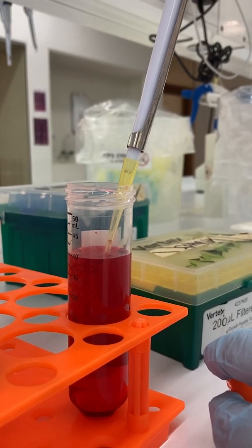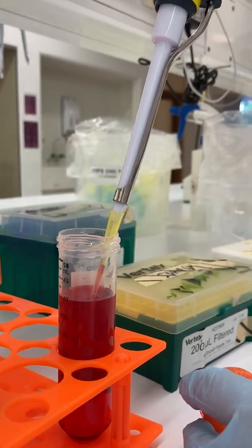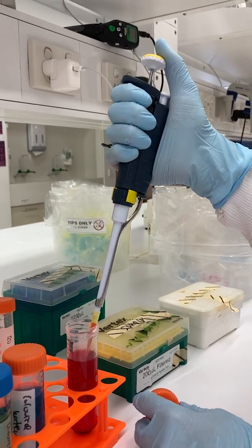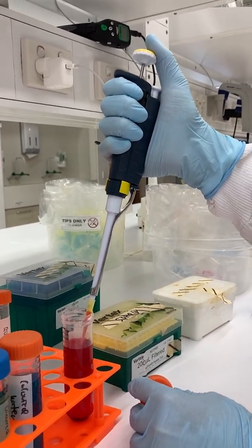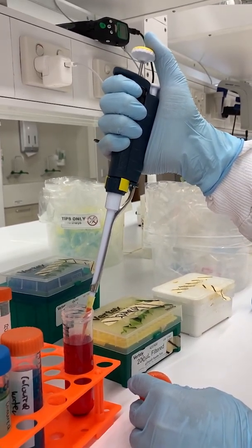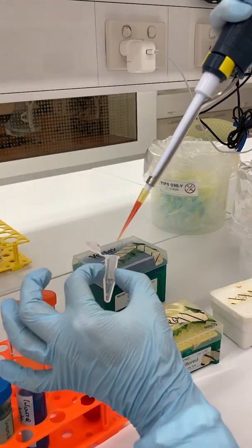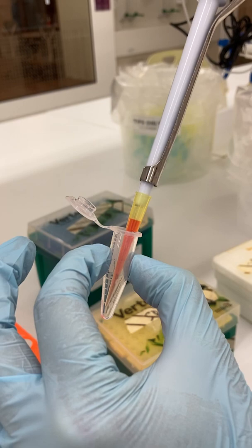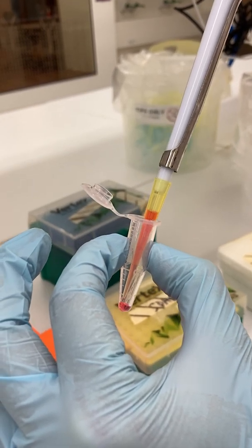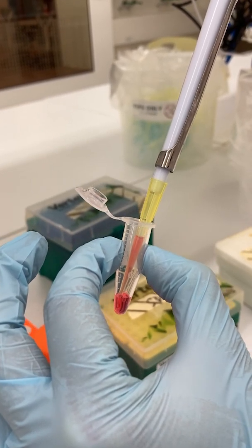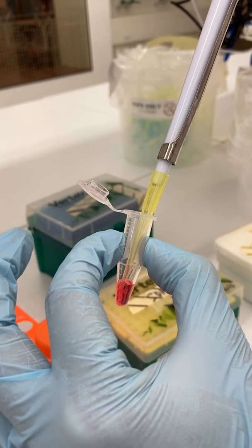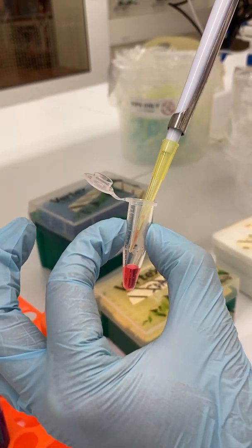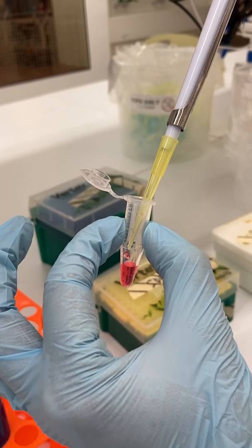Next, keeping your thumb down, insert the pipette tip into the liquid you wish to draw up, just below the surface. Now slowly release the plunger so that you draw up the liquid into the pipette tip. Place the tip of the pipette into the container you wish to fill. Then steadily depress the plunger until you reach the second stop. This forces a small amount of air out behind the liquid, ensuring that the tip empties cleanly.